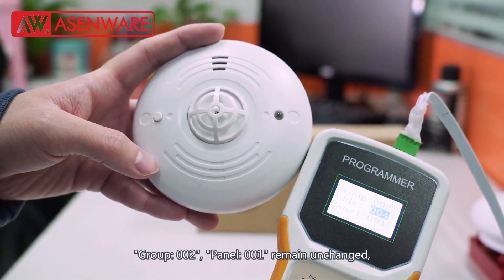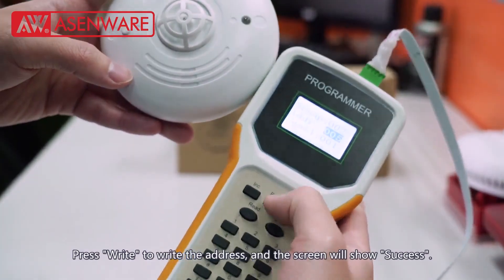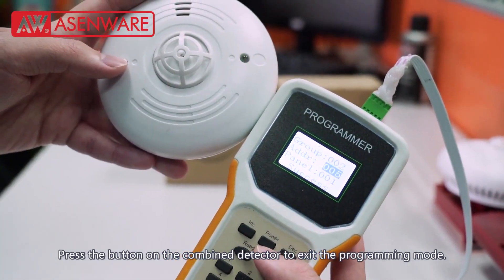Group 002, panel 001 remains unchanged. Press increase button to choose address 005. Press "Write" to write the address and the screen will show success. Press the button on the heat detector to exit the programming mode.